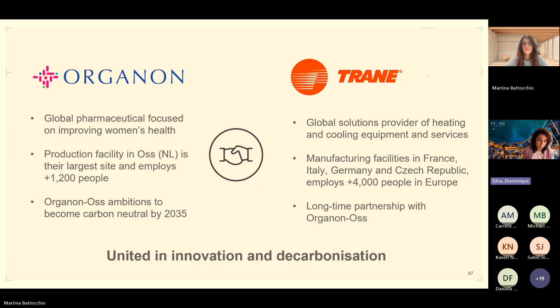The challenge for this facility wasn't just a sustainability challenge. Having a commitment is tough, but one of the big challenges was that the biggest barrier to meeting their carbon neutrality targets was actually their heating plant. Today, they have a heating plant of approximately 8 megawatts, provided by 4 gas boilers. Due to the nature of their production facilities and nearby offices, they have a profile where heating and cooling is required all year round, whether summer or winter.